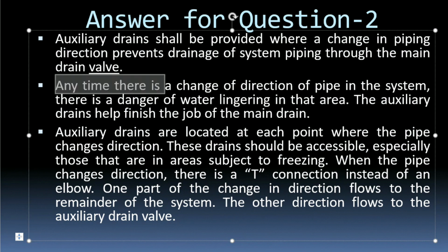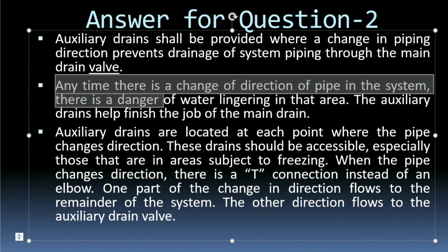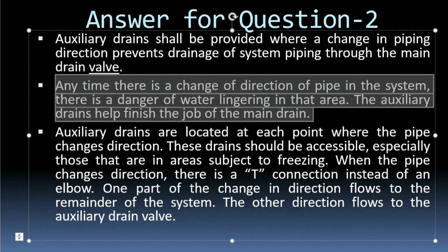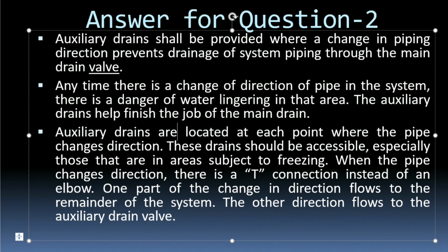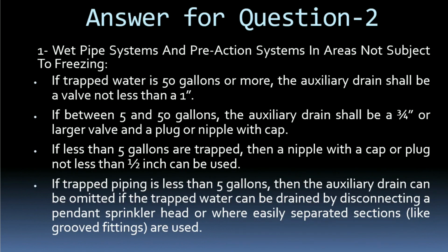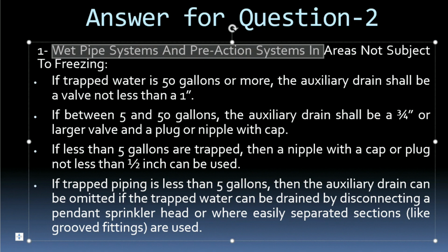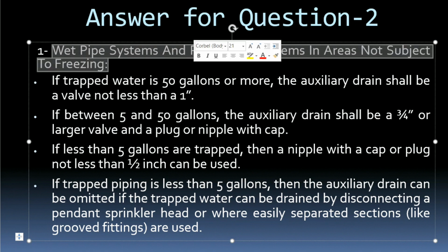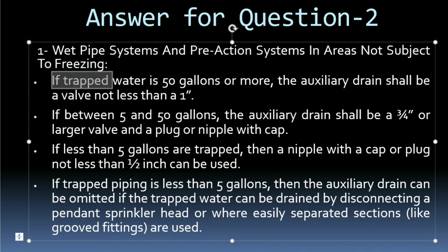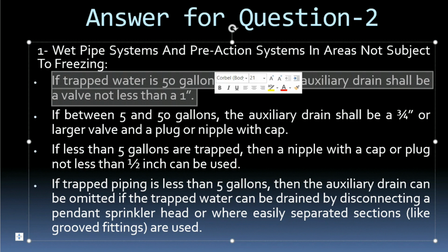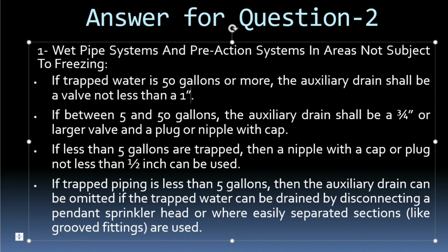So anytime there is a change of direction in the pipe system and there is a danger of water lingering in that area, the auxiliary drain helps to finish the job perfectly. And here, if you see, there are two conditions. The first one is for the wet pipe system and pre-action system in areas not subject to freezing. In that case, if the trapped water in that up and down area is 50 gallons or higher, then we have to use a valve of 1 inch.